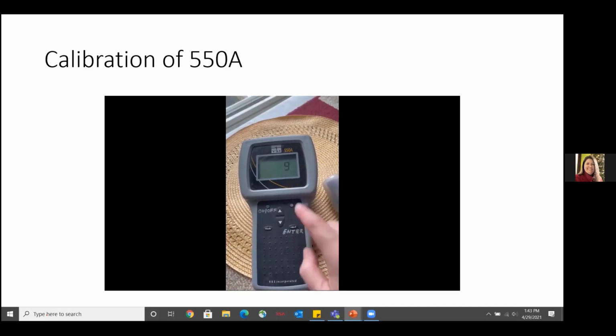So there's a 9. However, if I was somewhere else and the elevation was, let's say, 700, I would put the down arrow twice to get to 7. If it was 1,000, I would move it up a couple to get it to 10, and so on. Once you have the correct elevation, hit enter again, and your unit will begin calibrating.